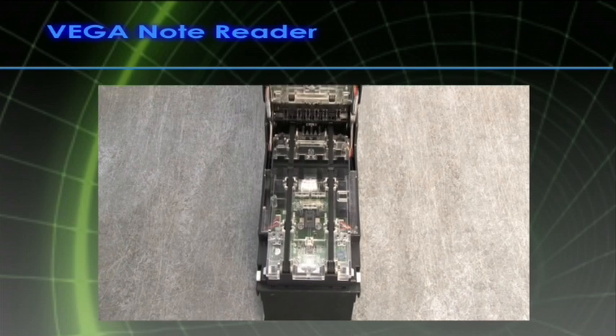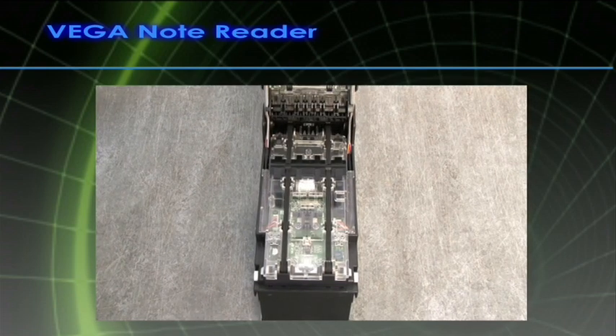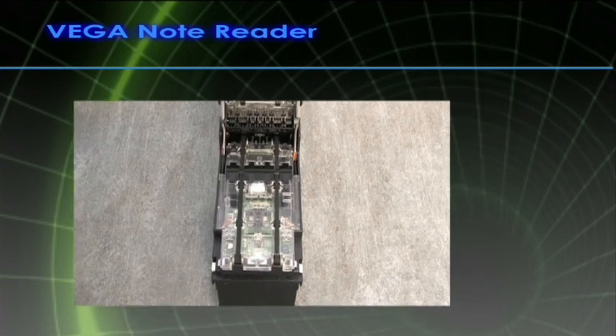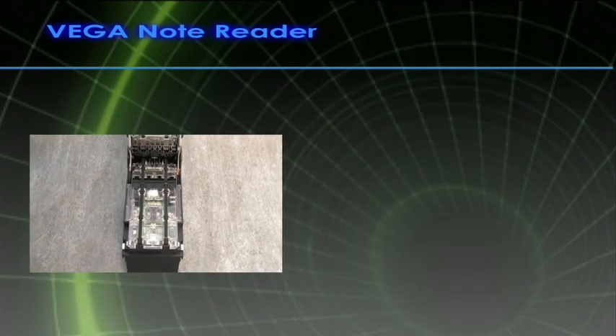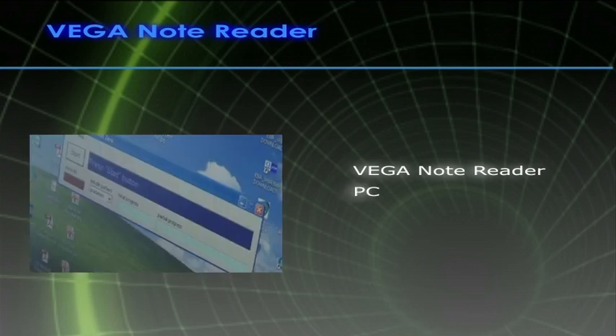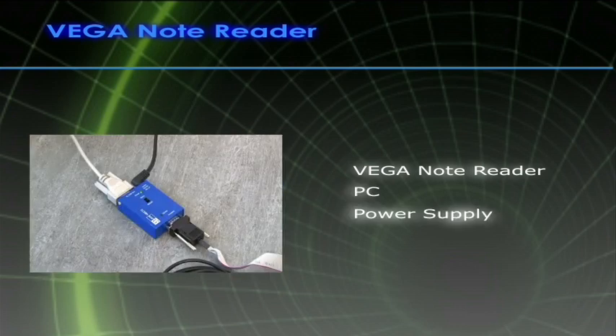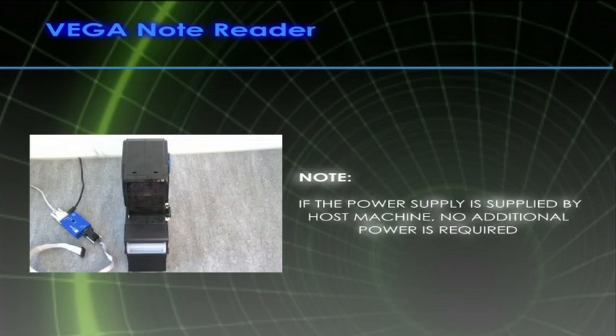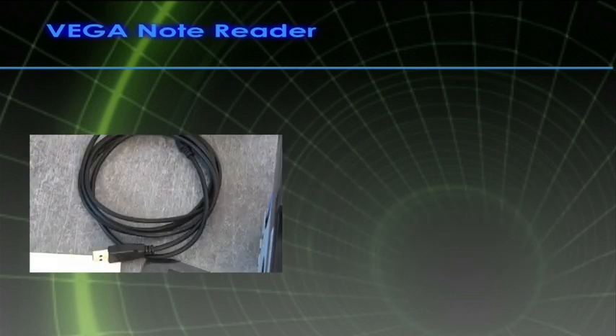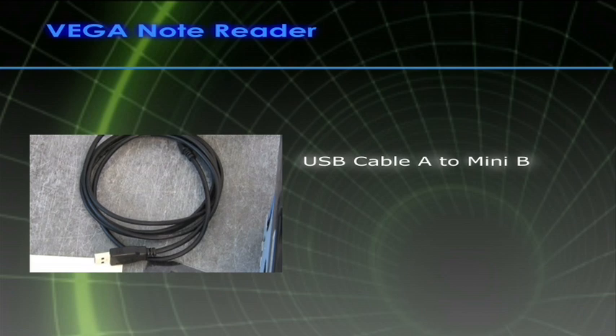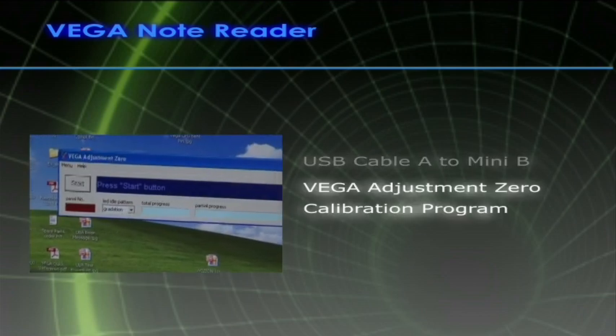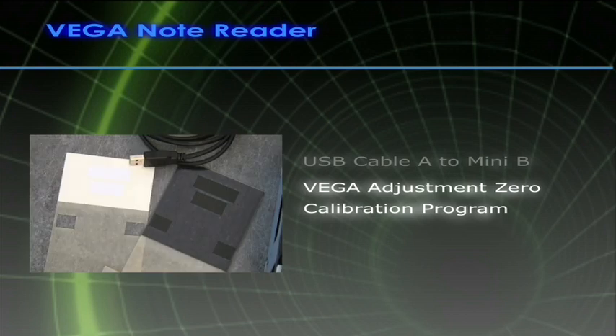If sensor boards have been changed or note acceptance is poor, calibration should be performed. For the calibration procedure, the following tools are required: Vega note reader, a PC, power supply. If the power is supplied via a host machine, no additional power supply is required. In addition, you will require the following: USB cable A to Mini B, Vega Adjustment 0 calibration program, white reference paper, black reference paper.